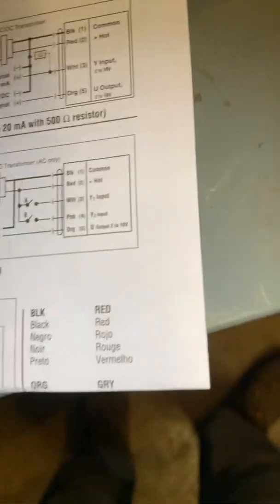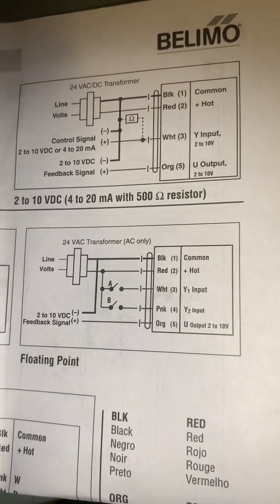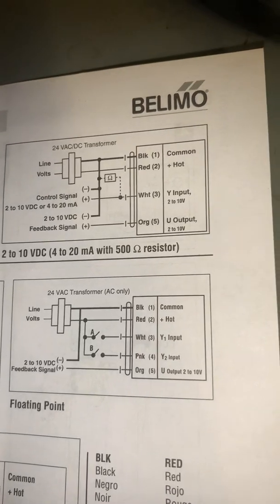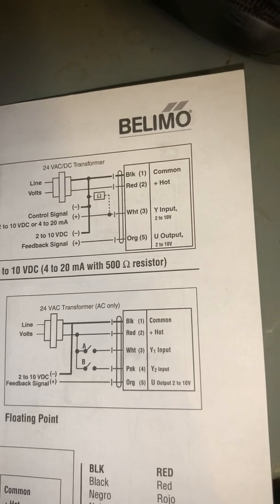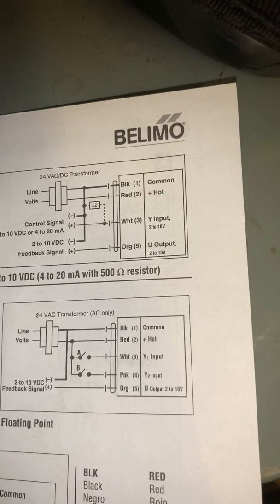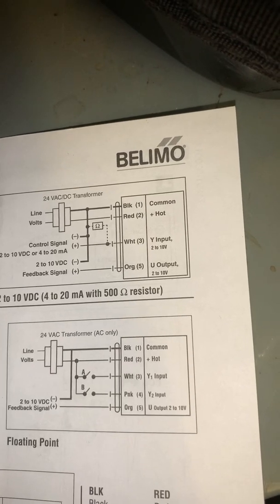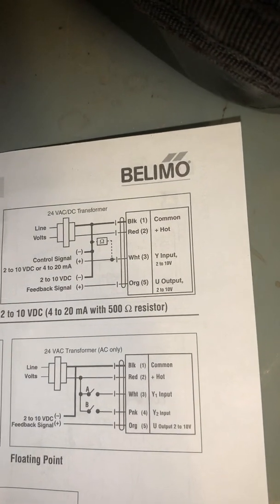So this is the way it's going to be wired. As you can see here, this is the transformer. Line volts — red, my positive, hot. Black, my common. White, my input from the control board, my DDC control board to the actuator. Orange is going to be my output signal from the actuator back to the control board.